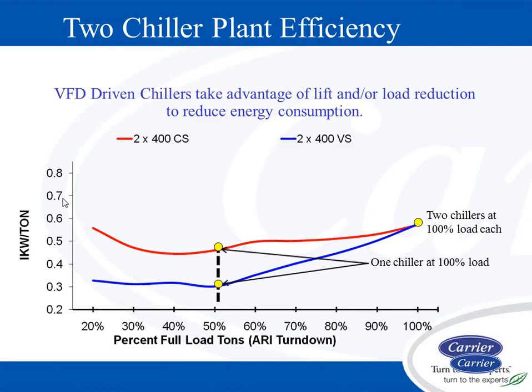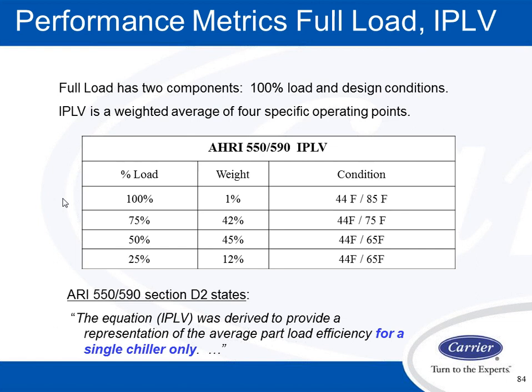As you hear me talking about variable speed drives on centrifugals, they track the weather. So as I'm at 50% building load, my condenser water temperature is reduced, so I'm able to reduce the speed on the centrifugal or screw, and therefore I'm able to run at lower kW per ton versus a constant speed machine. That's why VFDs make a ton of sense in this marketplace, because we can operate with cold condenser water temperatures a lot of the hours.